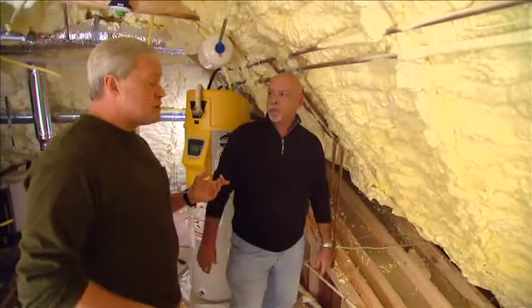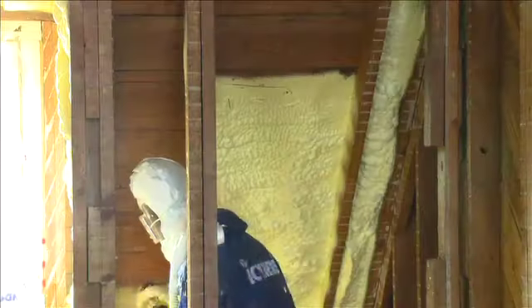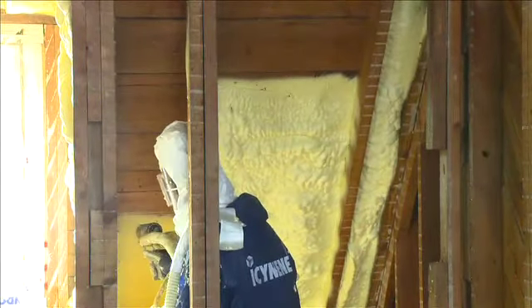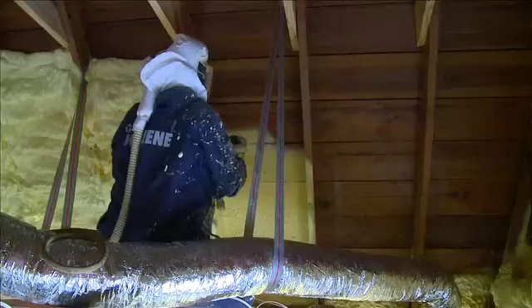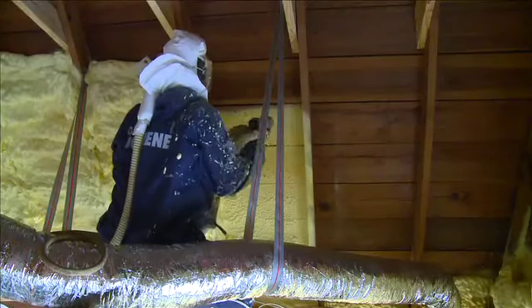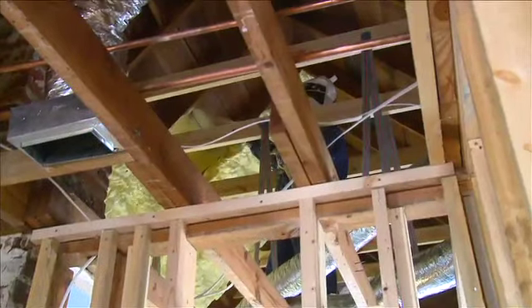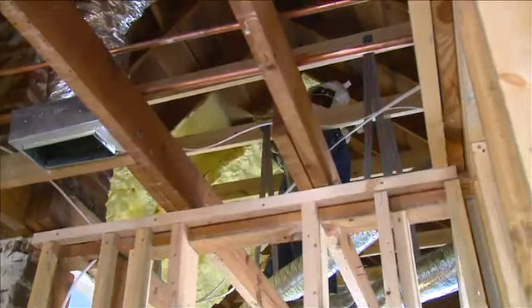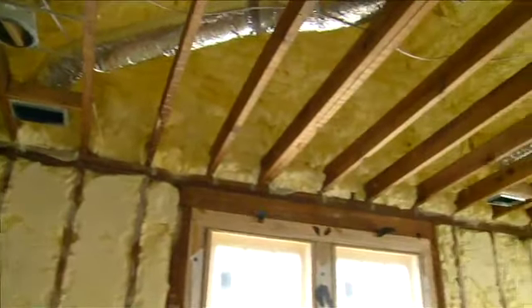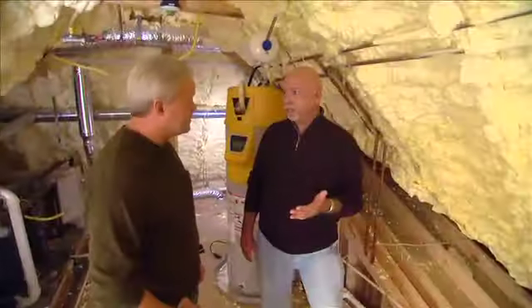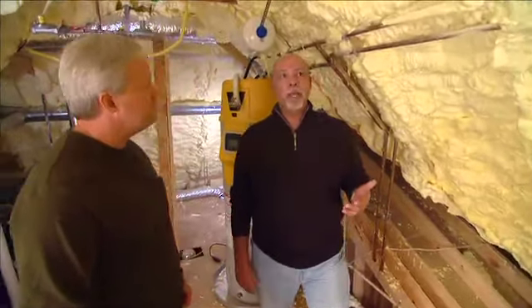Right. Another thing that surprised a lot of people, we've touted for years the importance of attic ventilation. Here, you're eliminating all of the ventilation. What we believe is that once you seal up the attic, no more outside air can penetrate into the attic, no dust, no pollen, and no excess moisture from humidity, which we have a lot of in the southern part of the country.